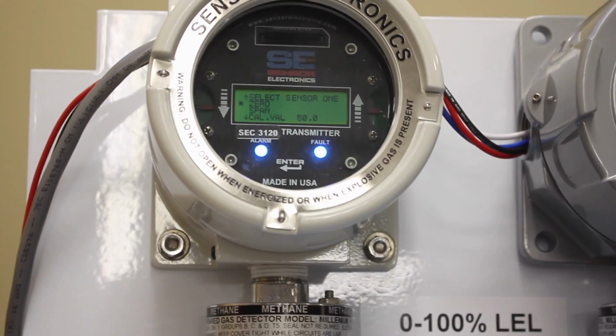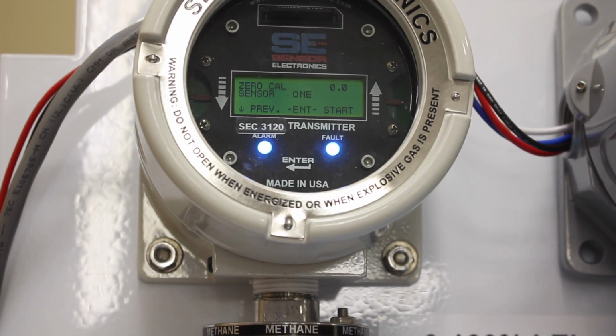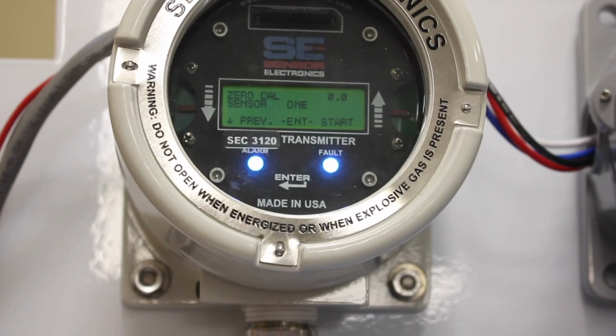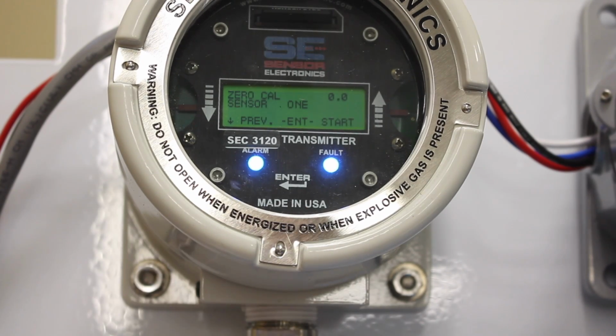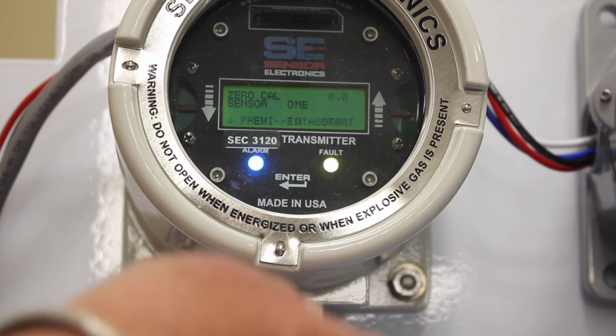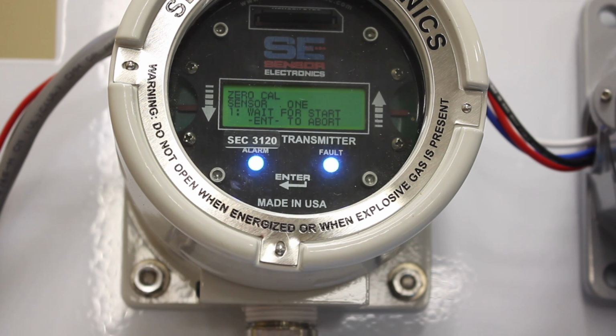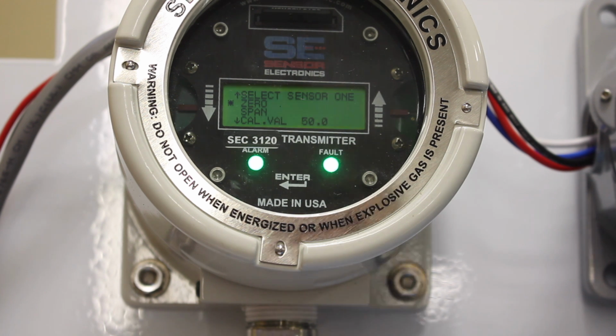So the cursor's on 0, we select enter, and you'll see the gas reading up in the right hand corner. Right now it's reading 0. So to zero the sensor, you go to enter again, and you'll see the little lights start toggling, and now the screen is saying 0 sensor 1 right now. And once it zeroes, it goes back to the normal state, and so now the sensor is zeroed.